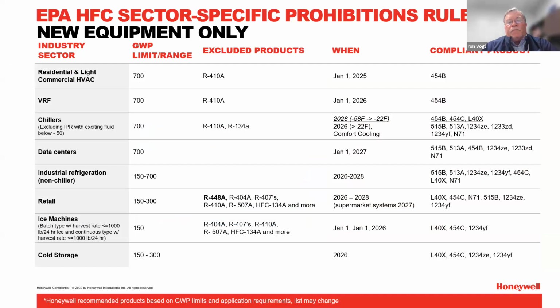This slide is looking at new equipment segments, what the GWP range is being set, federally, what products are currently there, when it's going to happen, and what you may use going forward. If we take a look at residential light commercial, there's a new level in place, which is 700. 410A, by the way, was a little over 2,000 GWP, so quite the drop down to 700.